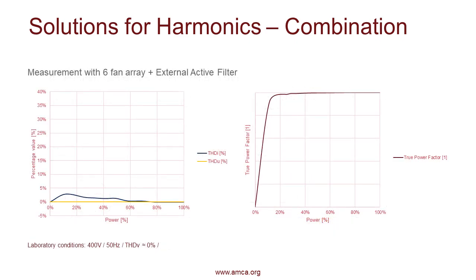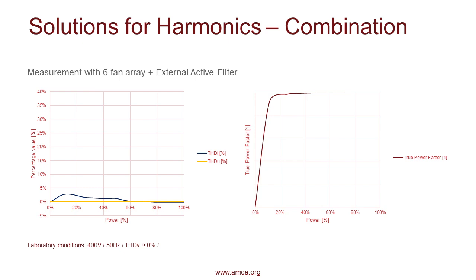So here we have laboratory conditions. We can see that at 80% or higher of the power percentage, the total harmonic distortion current is close to 0. And then it starts to slowly increase as it's going to a lower partial load, but it's still less than the 5% or even less than 4%. And you can see that your power factor is increased close to that 1. So this is a really optimal solution where you can get the best results, where you're utilizing the fans so they're not emitting any harmonics, they're not causing any problems, but then you're also using your external filter to help increase the power factor and reduce harmonic loads maybe on the system that's already existing.